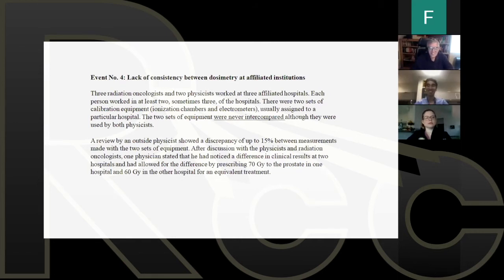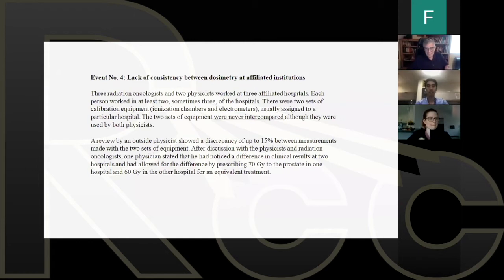So the doctor even noticed that there was a difference in tumor response because of that miscalibration from one center to the other. And the doctor compensated by increasing the dose in one center and decreasing the dose in the other center. Now this may work. Good for the doctor that the doctor realized there was a difference in clinical response, but that's not how we do things. We have to have accurate calibration and accurate reporting of radiation so that all physicians, all physicists, all clinical people have the same baseline for dose. 70 gray at institution one should be 70 gray at institution two. And the only way to assure that is by peer review, intercomparison, independent auditing of your calibrations.